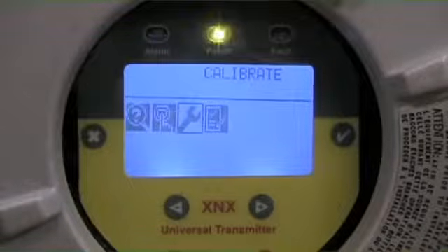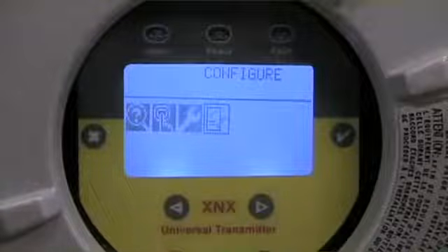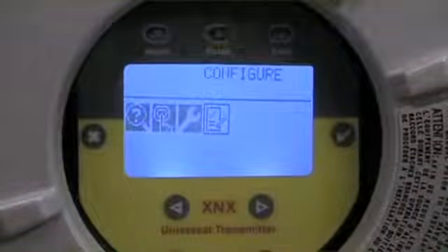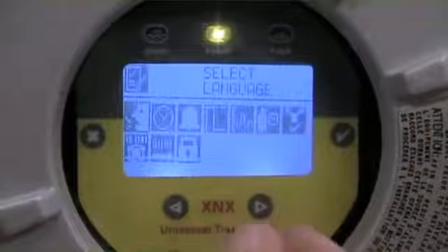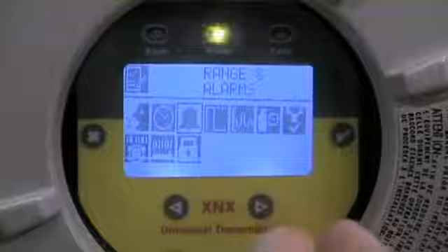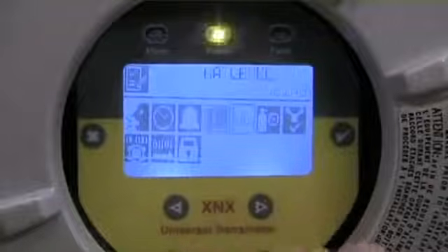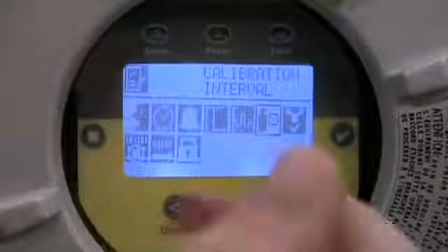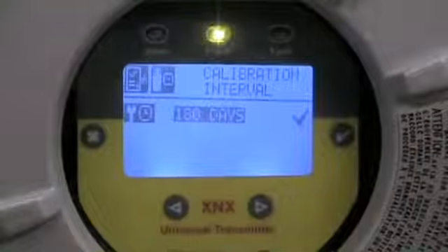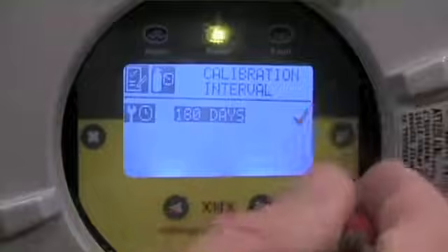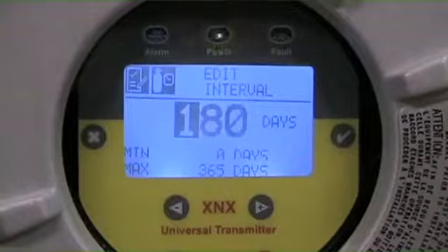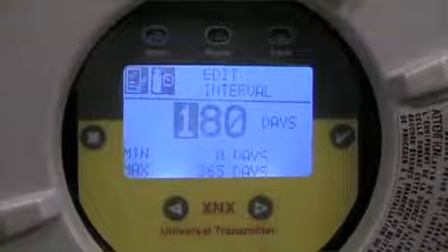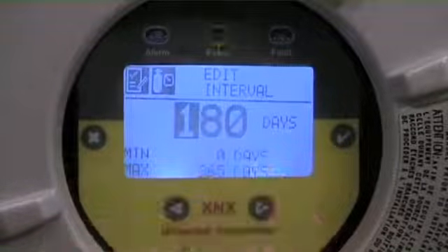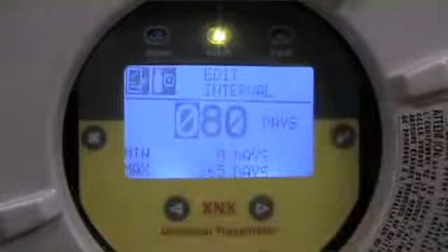To get to that point in the menu, we're going to move from calibration back into our configuration area. We're going to go into that configuration menu, and we'll scroll through these functions, setting the time, alarm levels that we've done in previous videos, latching functions that we talked about, and then it gets to a display for calibration interval. When that's displayed, check mark to accept, and you can see here that a default was set at 180 days. I'm going to enter that, and if my safety policy is that I want these calibrated every quarter, we'd simply put in a 90-day timer. So you'd index over to 90, make that your current requirement, and then accept that value.